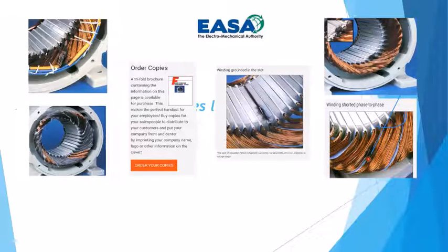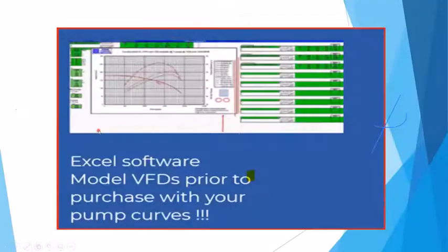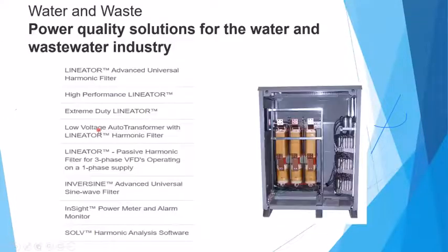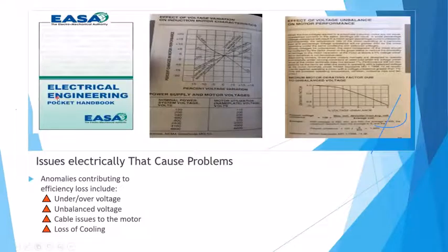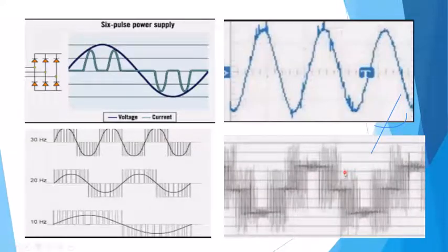There are better drives out there that have snubbing on the transistors. They're a little more expensive. And then you also have voltage to ground. If the voltage is getting too high, it wants to go the path of least resistance back to the steel stator, which is the ground. But again, it all has to do with this created static out there. So again, back to the issue about total power, it's important to look at what we are actually seeing for total power. Let's see if I have any other questions I missed here.